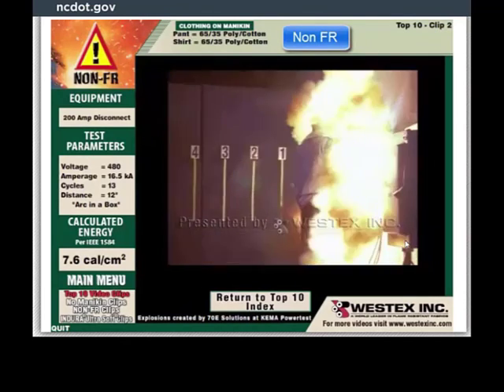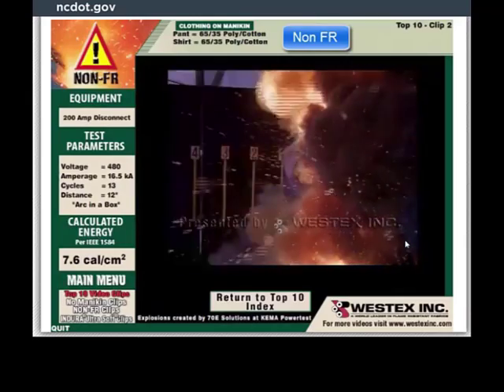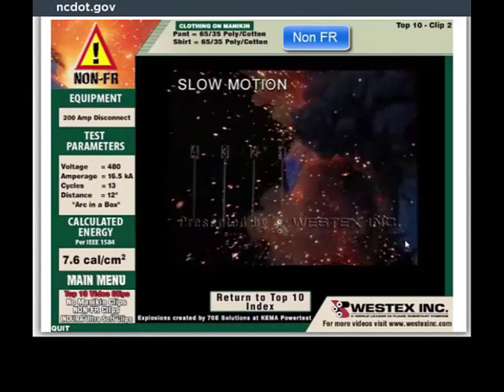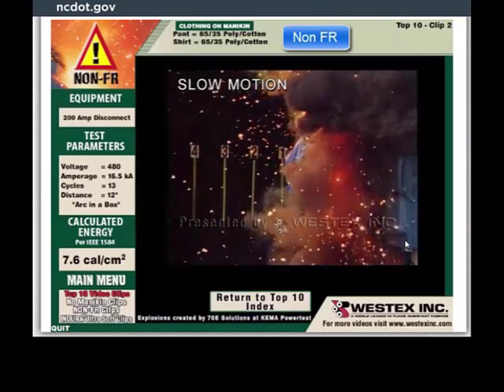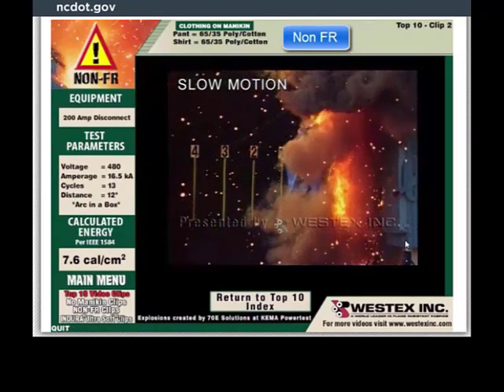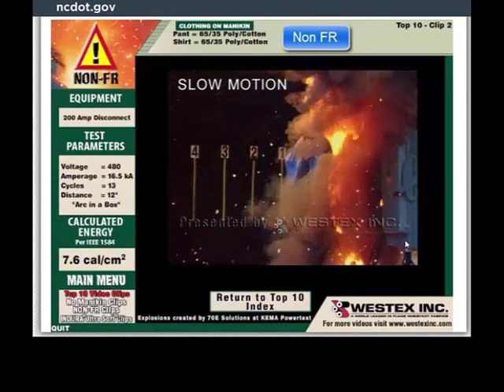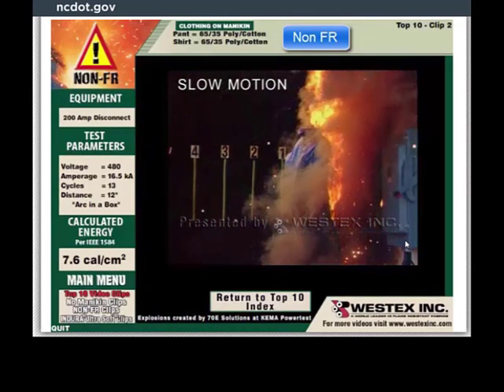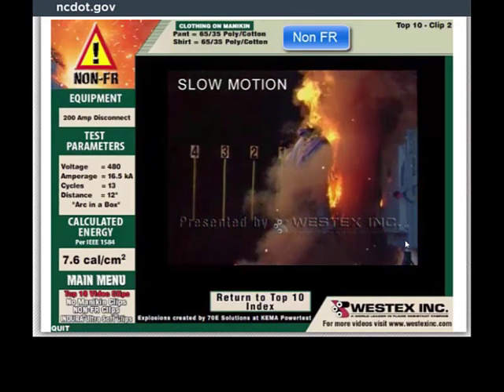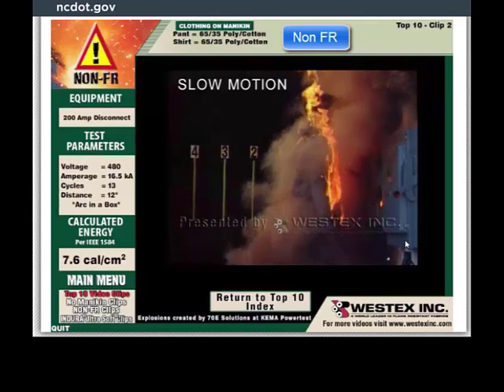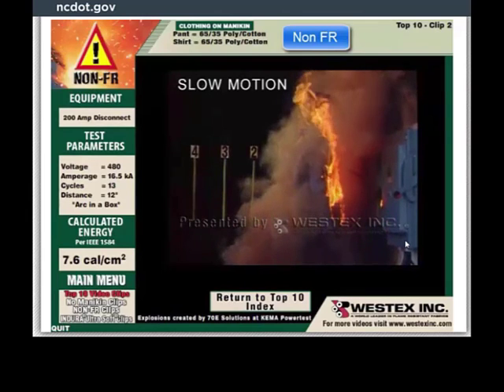In slow motion, you have an excellent look. You can see molten metal hitting the lens of the camera from 22 feet away. The camera's 22 feet from this arc, and molten metal droplets are hitting it. Before the molten metal has even completely cleared the air, the garment is on fire. What you're looking at now is fire, not arc. And a clothing fire this violent is going to dramatically worsen injury.